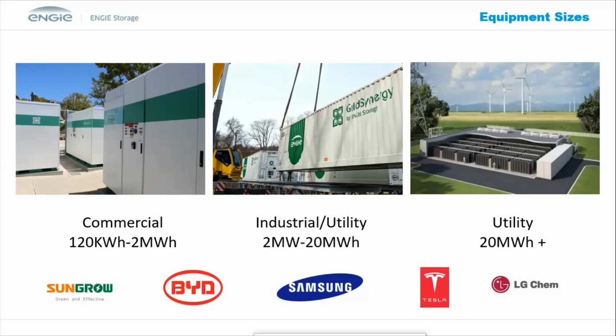We work with a lot of different technology players in the market. We still do Tesla, though they have some supply constraints. When choosing technology, it depends on a couple things, not just cost—it depends on the chemistry being used. In high desert or high heat environments, we tend to go lithium iron phosphate, so we do a BYD system because it performs better in high heat. If it's not a high heat situation and it's standard usage, we may go Samsung or Tesla, which tend to have better density and perform better in less volatile environments. So it varies a bit based on the chemistry you choose, the utilization, the load, and how you're using the batteries.